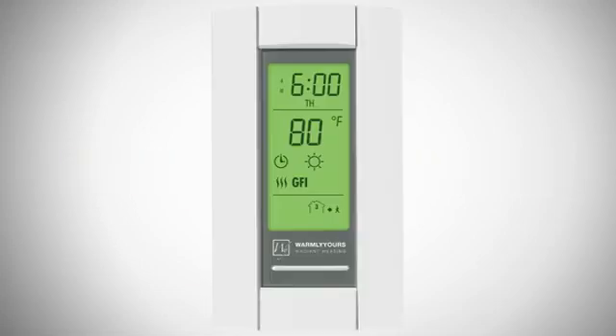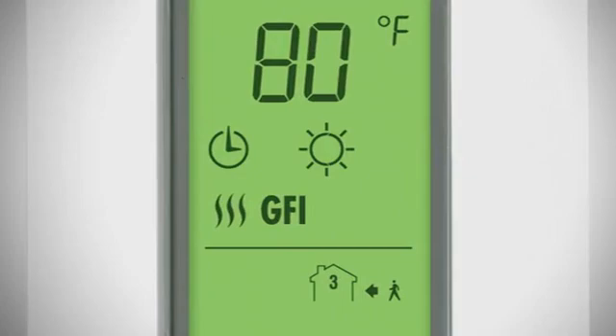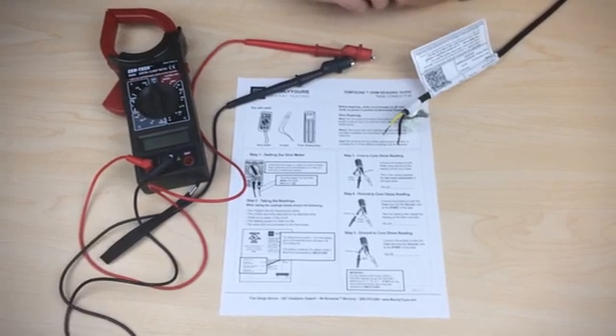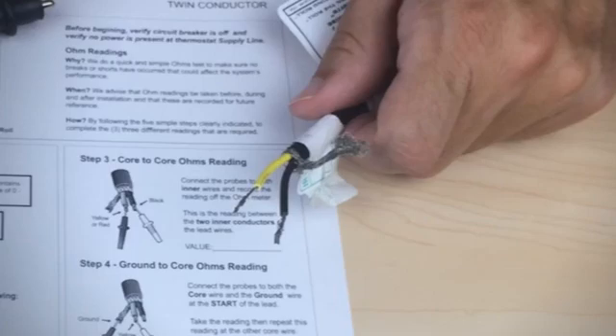If your thermostat displays GFI on the screen, it's telling you that it thinks it sees a ground fault. That ground fault sometimes is in the wire that's coming up from the roll or the system in your floor.